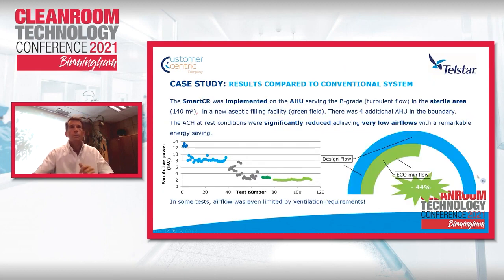Well, we made a case study. This case study is related to a facility that we made. It's an aseptic filling facility. It was a greenfield. The sterile area is only 140 square meters, but although there is a main air handling unit serving this area, there were another 4 air handling units on the boundary affected by this one.